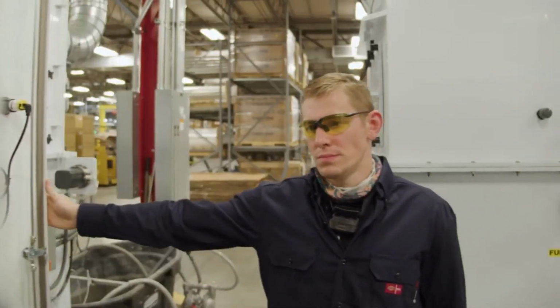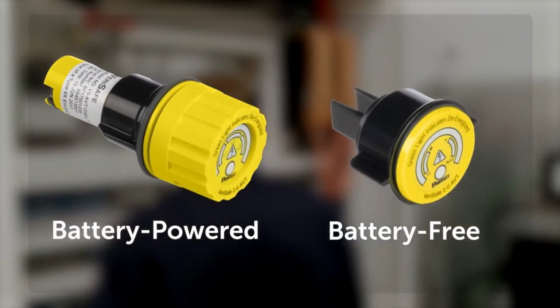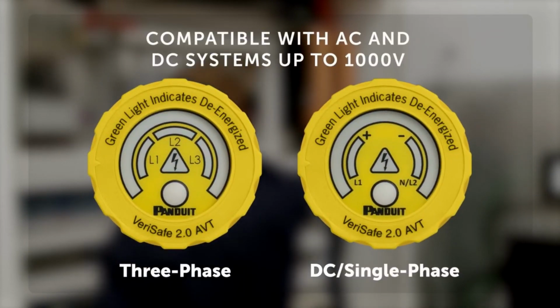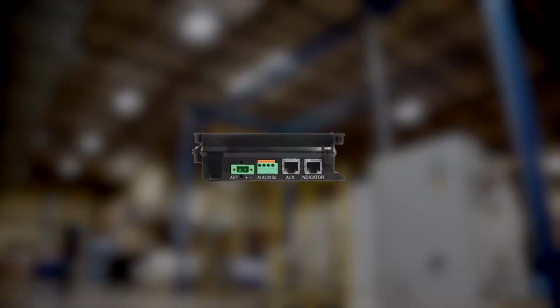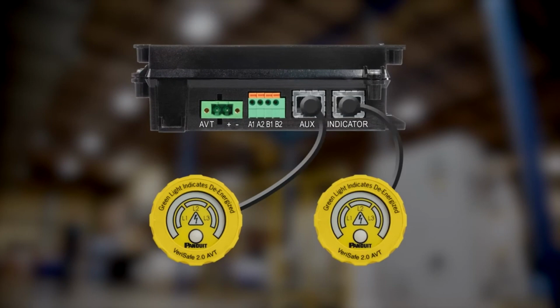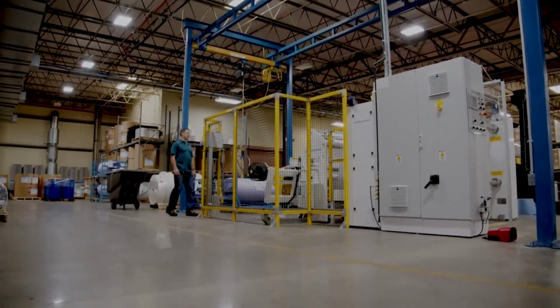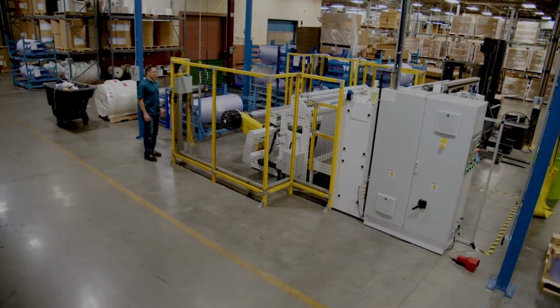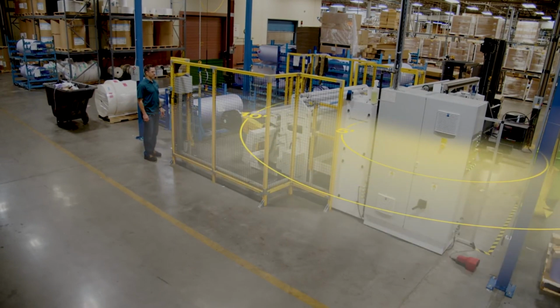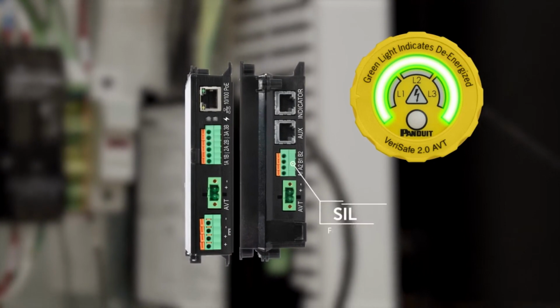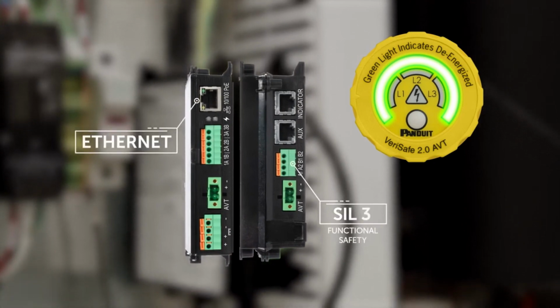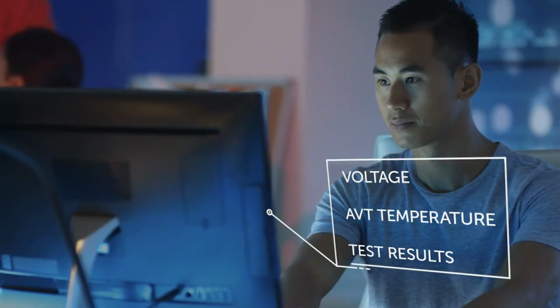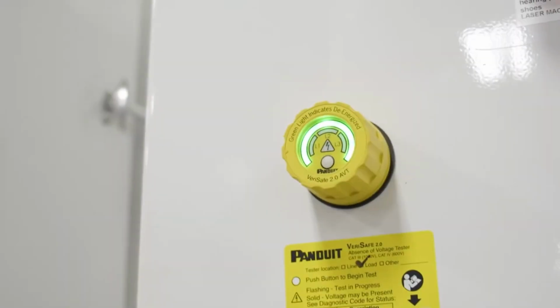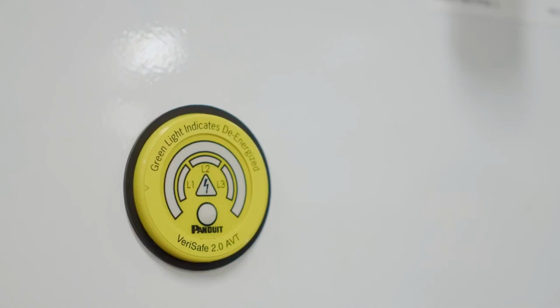The 2.0 AVT is designed with flexibility in mind. You select the options that best suit your needs. All VeriSafe AVTs test for absence of AC and DC voltage. The 2.0 AVT supports two indicator modules, allowing the test to be initiated from more than one location. Put extra distance between the operator and the hazard by installing the second indicator at the entrance to a controlled area or outside the arc flash boundary. Integrate the AVT into your control system, utilizing Safety Integrity Level 3 solid-state contacts or an Ethernet connection. Monitor voltage status and troubleshoot remotely with the optional network module. Safeguard your employees, your equipment, and your bottom line with a family of products utilizing VeriSafe's groundbreaking electrical safety technology. Operate faster, smarter, and safer with VeriSafe AVTs.